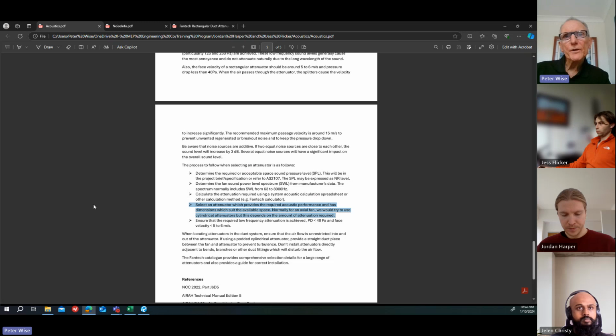Then we go and select an attenuator which provides the required acoustic performance and has dimensions which suit the available space. So if the attenuator is going into a ceiling space, you need to be aware that there are restrictions on the height and perhaps the width. Then we need to work through that to get an appropriate size. On a big project, sometimes attenuators can be very large, and we may have to break it down into 2 or more attenuators in series because they're just too big to handle, too heavy. That's probably something you're not going to see soon, but on a large project that can happen. So we've got to think about how the guys on site are going to manage to get these attenuators into place.